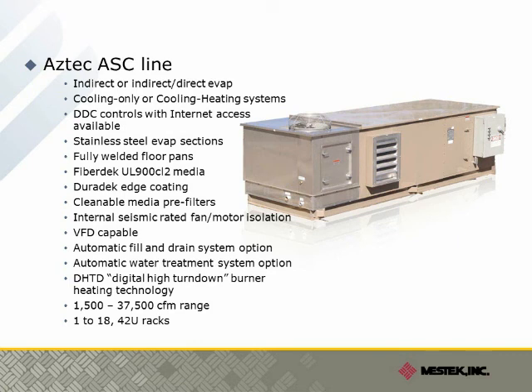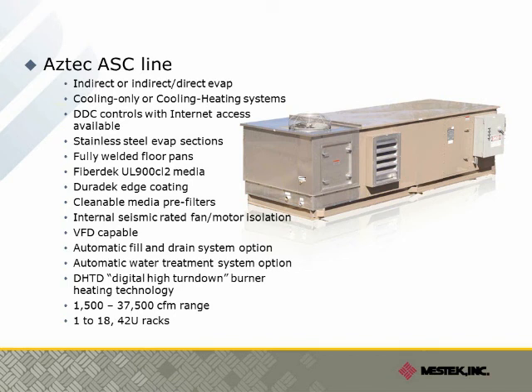The product that can make that kind of difference is the Aztec ASC product line. In addition to basic characteristics such as stainless steel evaporative sections and welded floors and drain pans, this line includes features well suited to data center applications. The integral DDC controls with monitoring and remote access allow data center personnel to focus on the server side while facilities teams focus on the HVAC equipment even if not physically on site. The Fiberdek evaporative media is a glass fiber-based media that is flame and fire resistant when it dries out — important for times of year when evaporative cooling is not needed and there is no water flow.